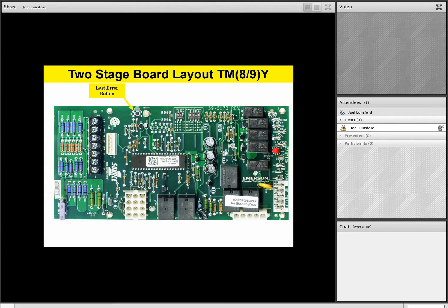Right next to the last error button is a status LED to retrieve flash codes. And again, this is a tricolor LED. It'll flash either yellow or amber, it'll flash red, or it'll flash green based on the flash code that we're observing. As we move around the board, we see we have a continuous on-fan speed selection. And again, this is a really nice feature because if the homeowner goes to fan on at the thermostat sub-base assembly, these dip switches will allow us to select how fast the fan runs if they go to a fan on or continuous fan operation.